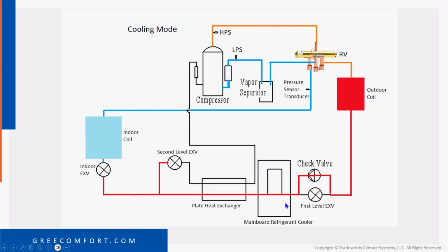And then this main refrigerant cooler. When we get to the equipment, which we're going to get to shortly, you're going to see the board in the front, where it's got the liquid line going all across an aluminum channel across the front of that board. That's what's cooling the inverter driver. It's not an air-cooled inverter driver. So that's what they mean here by main board refrigerant cooler. Then it goes into the plate heat exchanger, depending on conditions of the unit. So it depends on whether or not the subcooler is actually being used.